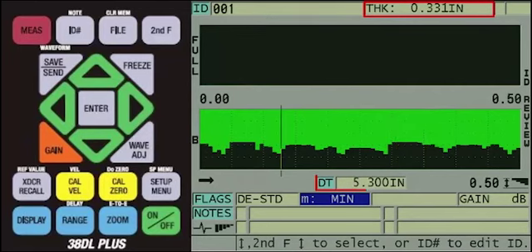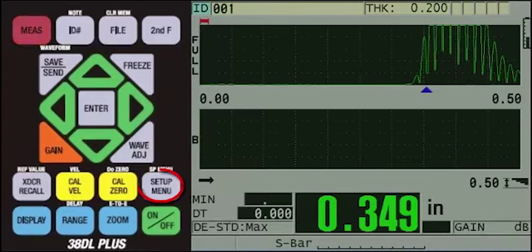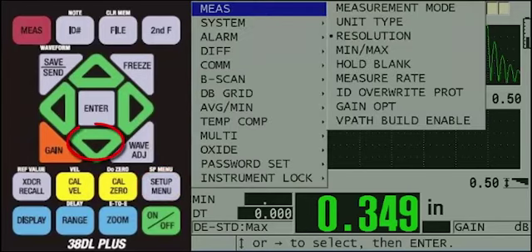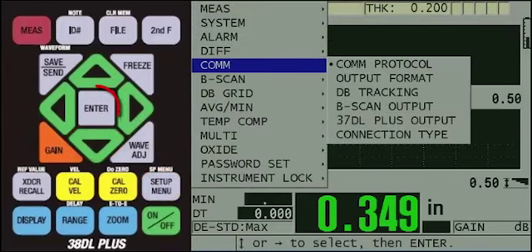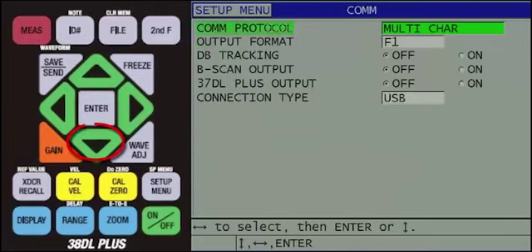If you then connect the 38DL Plus to the Gauge View Thickness Interface program, you can transfer the B-scan file and review it within Gauge View Thickness. In order to transfer the B-scan data, you first need to turn on the B-scan output in the communications setting of the 38DL Plus. To do this, first press the red Measure key to exit ID Review, then press the Setup menu key, then keep pressing the down arrow until you highlight COM, and then press Enter. Then press the down arrow to highlight B-scan output, then press the right arrow to turn it on. Then you can press the red Measure key.